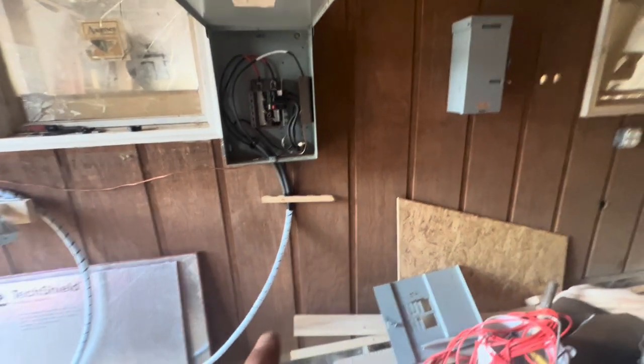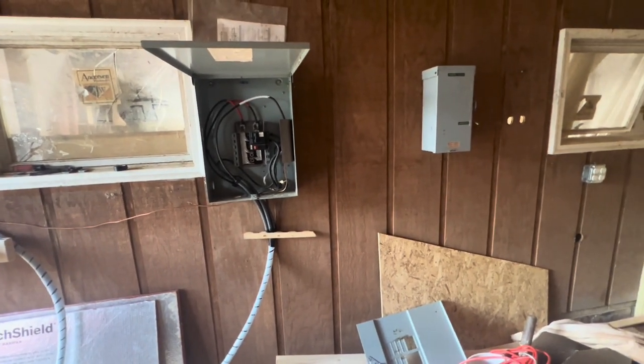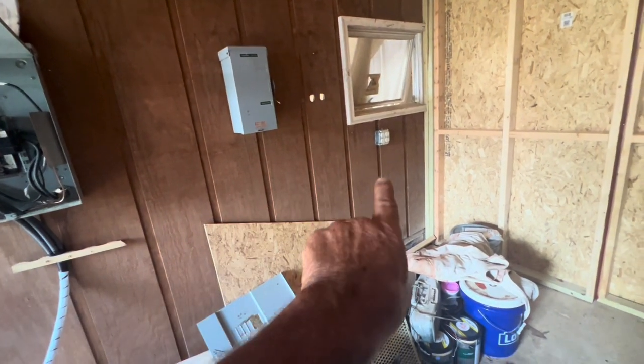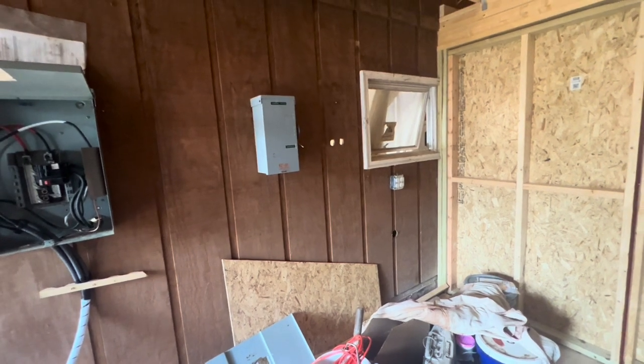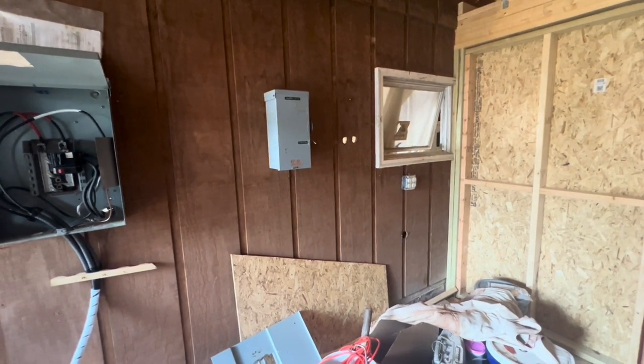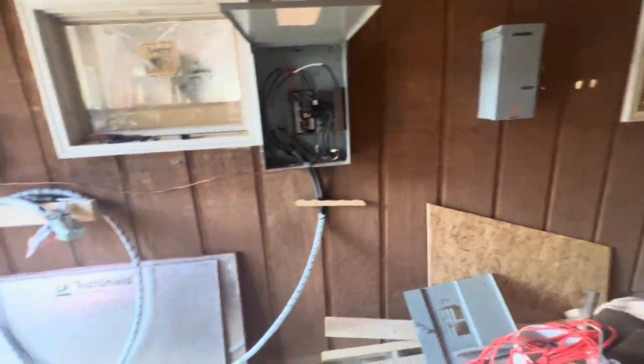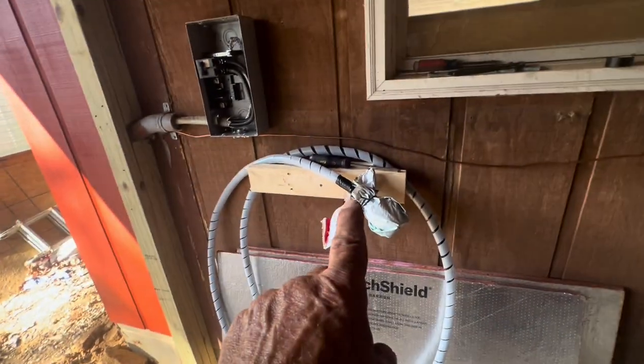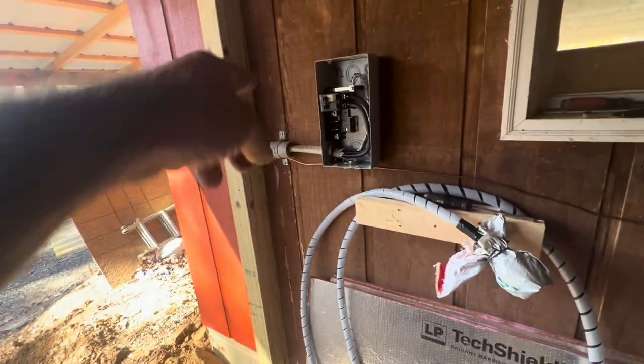In the future, the generator will run that house. They have a big wood-fired furnace that has to have electric all night long. So what we're going to do is — this was the disconnect for the generator going to an inverter — we're going to put some lithium batteries here and an inverter. They'll be able to switch to the inverter at night to power the pumps for the hot water boiler to keep it from having issues, or run the generator. Being this thing has a 100 amp plug and a 50 amp plug, we're going to run the 100 amp plug to that house and wire a 50 amp cord and plug to run the other house. Basically, that's all it is to it.